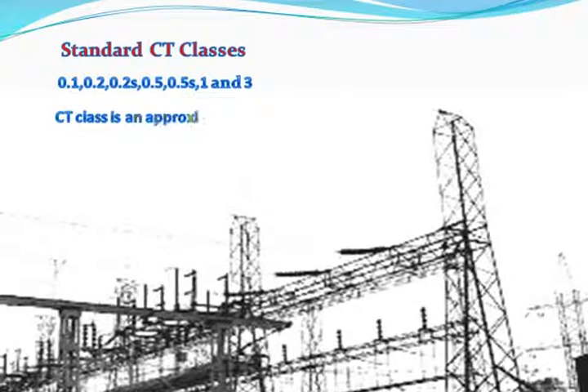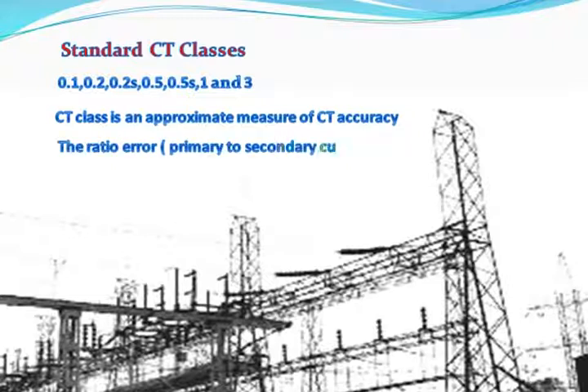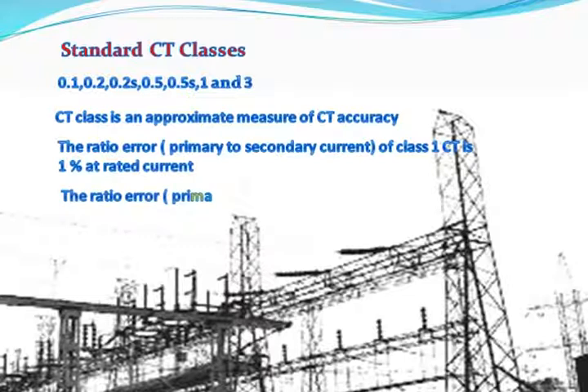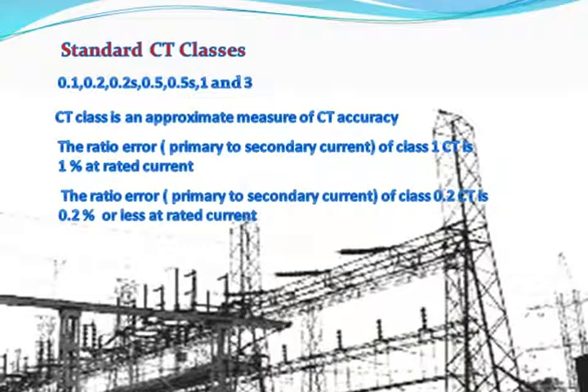CT class is an approximate measure of CT accuracy. The ratio error, that is, primary to secondary current, of a class 1 CT is 1% at rated current. Similarly, the ratio error of a class 0.2 CT is 0.2% or less at rated current.